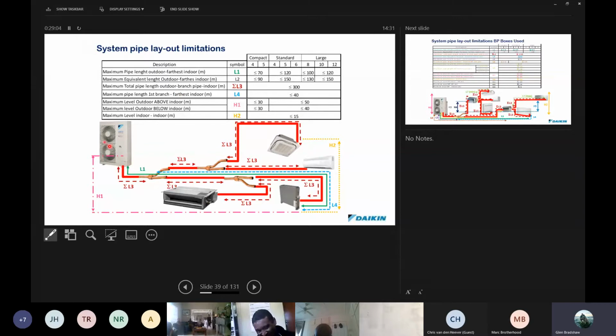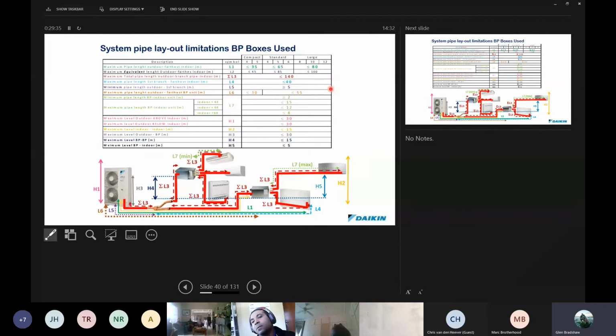Okay, you'll see here this is VRV, a mini VRV, and here you'll see the piping lengths also slightly different on there. Okay, the maximum indoor to indoor height of 15 meters. Okay, and a maximum length of 120 meters or less. Okay, 70 for the 4 and 5 horsepower, 120 for the 4 to 6, less than 100 meters for the 8, and 10 and 12 also for 120 meters.